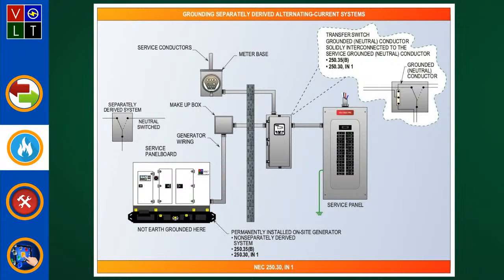We tell you that the generator shall not be grounded where the transfer equipment does not switch the ground and neutral conductor, and where the ground and neutral conductor is solidly interconnected to the service-supplied ground and neutral conductor.